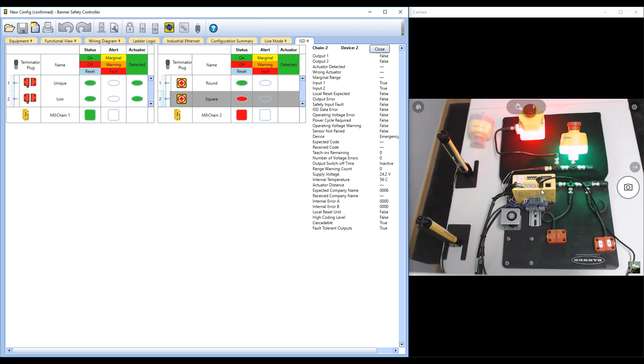But if you just want to hook up an RFID switch, an E-stop, or even a string of them, you can have 32 RFID door switches or 32 E-stops connected to a standard controller, and the OSSDs will work just fine with a standard relay, a different safety controller, or a safety PLC. It's all good, it all works. You just won't get the in-series diagnostic data unless you have something that can decode it, like our SC10 or the IO Link module.